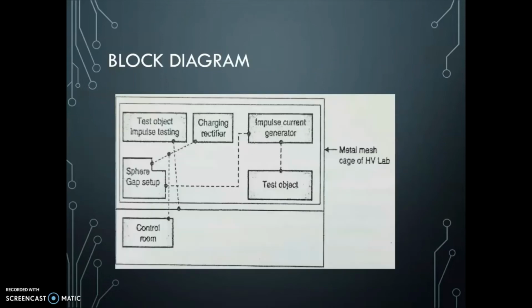As we can see here, there are multiple components in this block diagram of the single point grounding system. We can see the test object, impulse testing, charging rectifier, impulse current generator, sphere gap setup and control room. These are connected in the manner shown in the block diagram. In impulse testing, high currents are involved. These currents may interfere with control gear in the lab and can cause damage and safety hazards to the users.